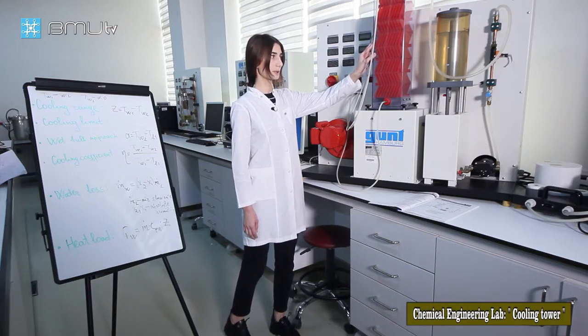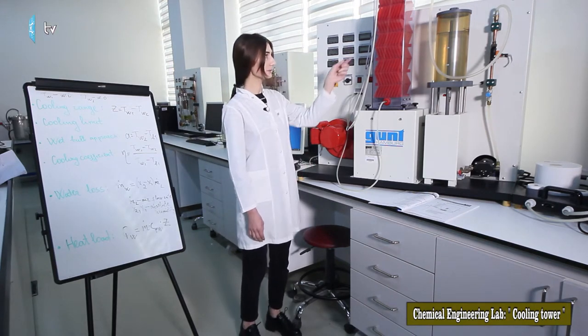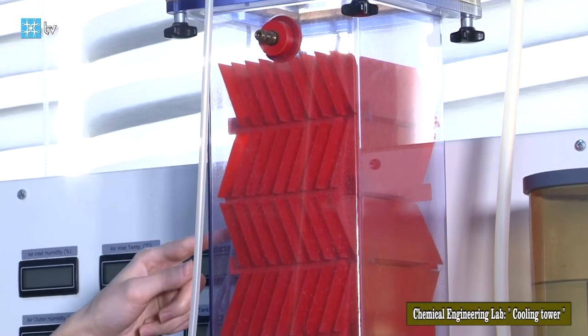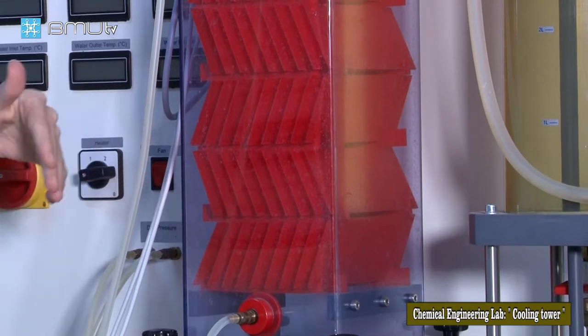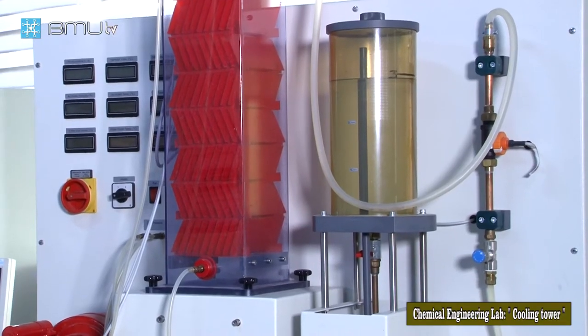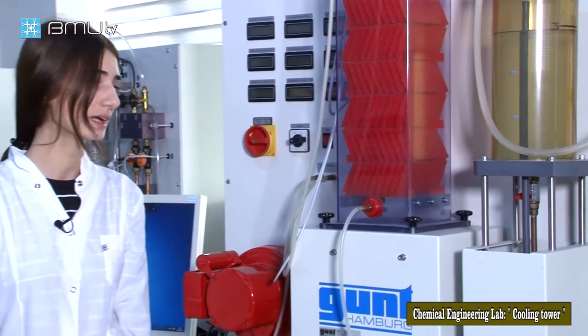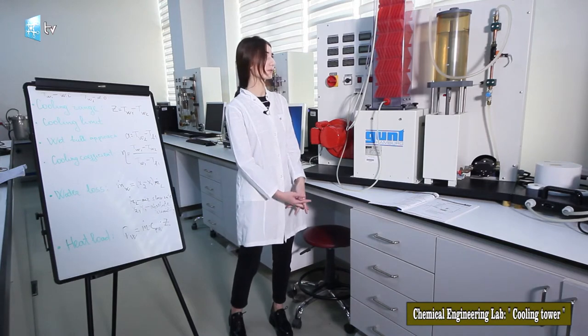The cooling column is transparent, allowing us to observe the process clearly. There are slats inside it which are arranged at angles to each other. The aim of this part is to increase the surface area and give maximum time for water and air to contact each other. The cooling performance of the device depends on its design. The packing density is one of the most important characteristics of the cooling tower, because it affects the cooling capacity and cooling efficiency of the device.